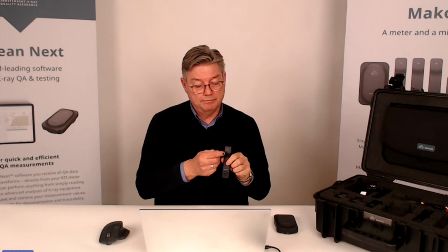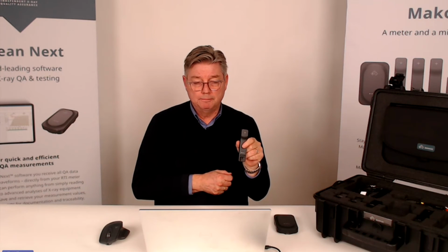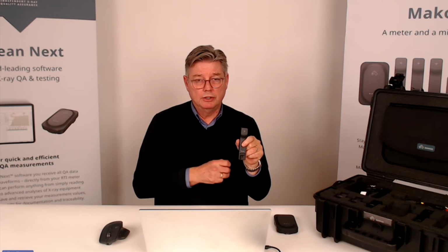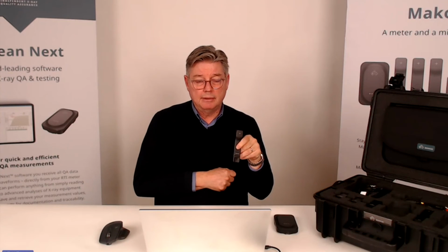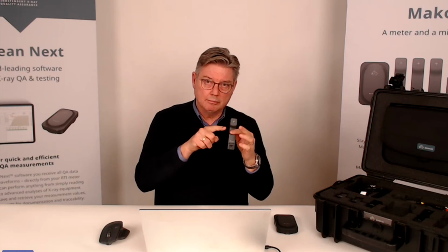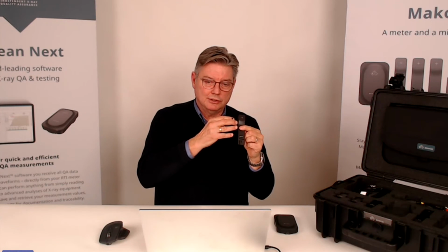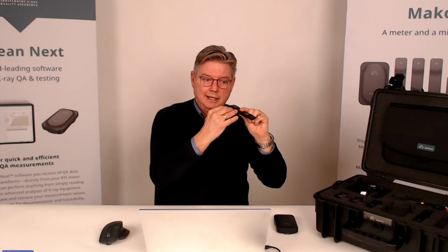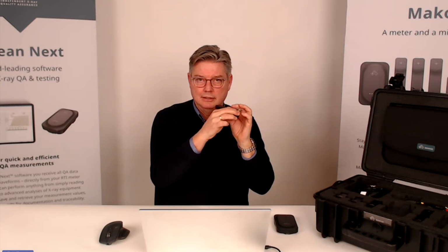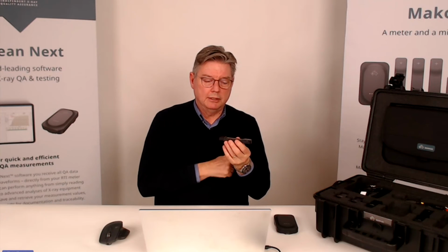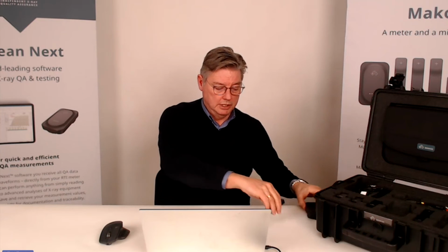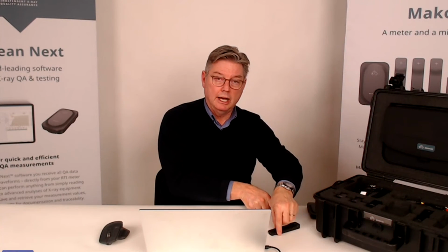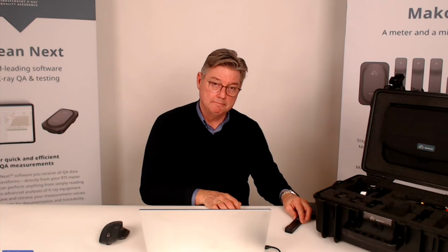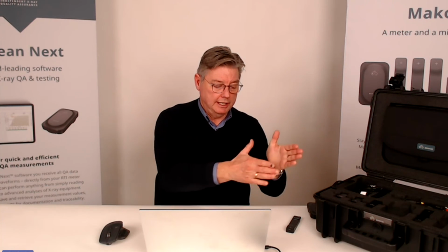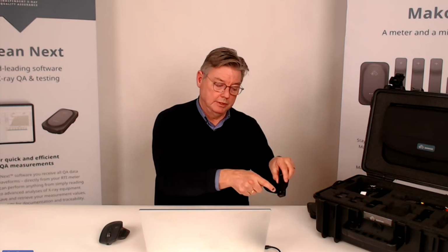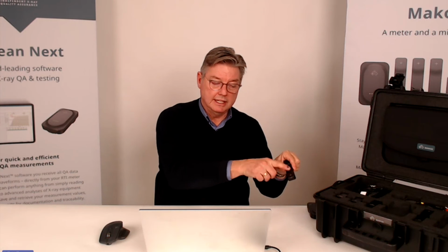Regarding the detector, as you saw on the slide of the detector design, the active area is 7 by 7 millimeters, so it's square. The diodes are in different layers. That means that if you turn it like this, there's no change in the heel effect. The heel effect does not do anything, so we can place it in any direction on the bucky. It doesn't really matter how we rotate it on the mammo bucky. It will give the same reading as long as we have radiation on the active area. So the active area has to be irradiated, and as long as we have that, we're okay.